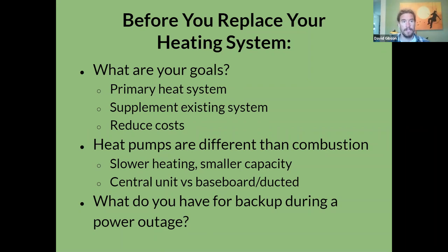They're meant to run continuously. So you generally don't want to set the temperature back when you leave or at night. You want to let it just run continuously, and it maintains the temperature in the space. Heat pump systems generally have a much lower heating capacity. They're much more of a low and slow versus a hot and fast type of heat. And so they won't reheat your house quickly. If you turn the temperature down 5 degrees, it could take a few hours to reheat the space depending on what the outside temperature is.